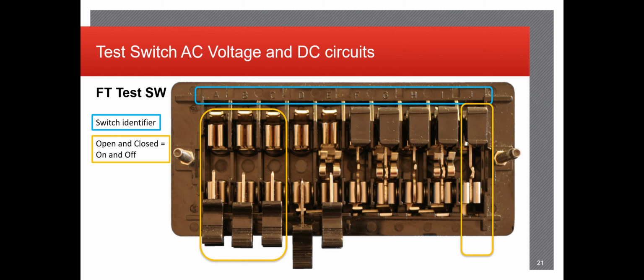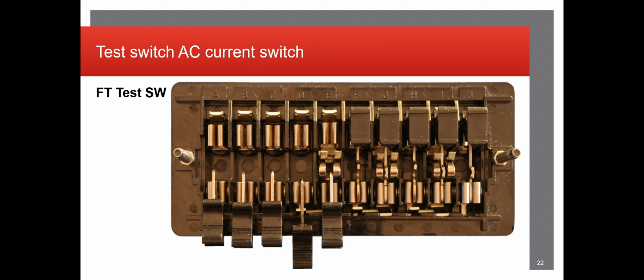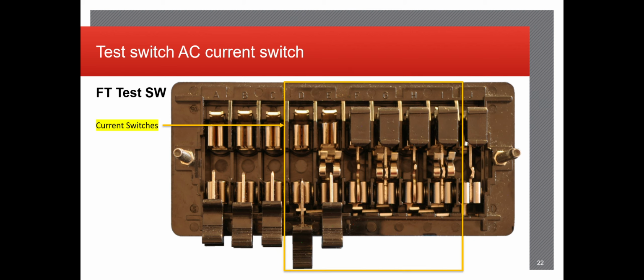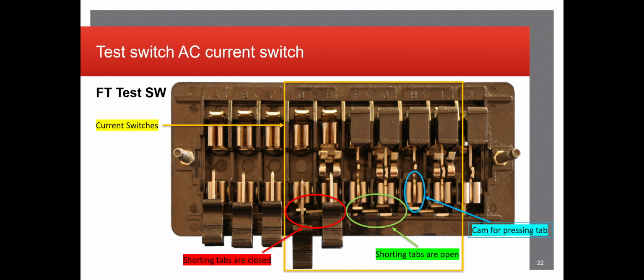So up top, like I said, the switch identifier specifically is the letters, and they show you examples of the switches open and closed as well. This will dictate whether you have power running up to the relay or whatever circuit the switches are connected to or not. We have the example for the current switches as well. As I said, at the base of them, the shorting tabs, whether they are open or closed, if the test switch is open, as you can see on test switch D and E, the shorting pins push the shorting tabs down and create, like I said, create a short.